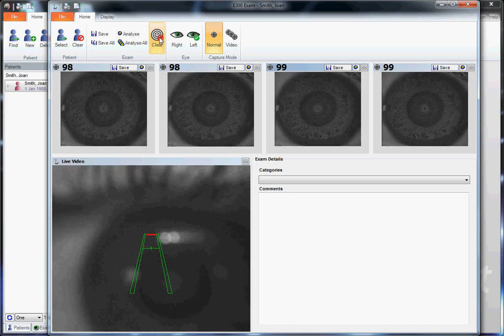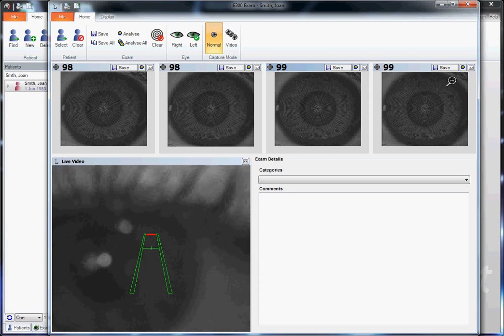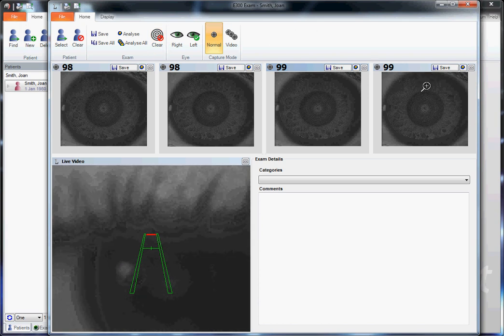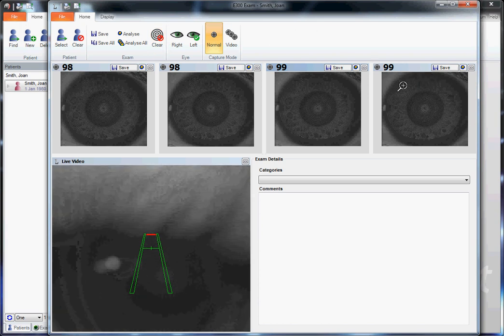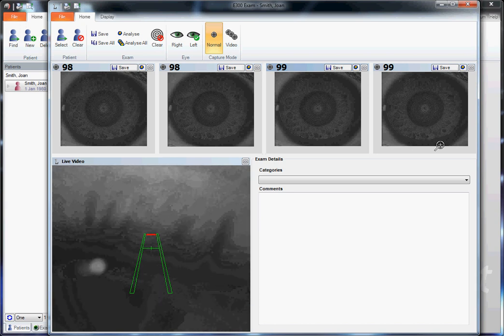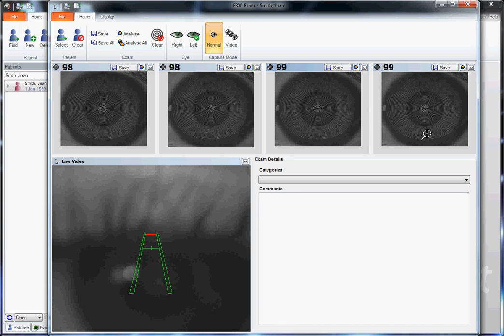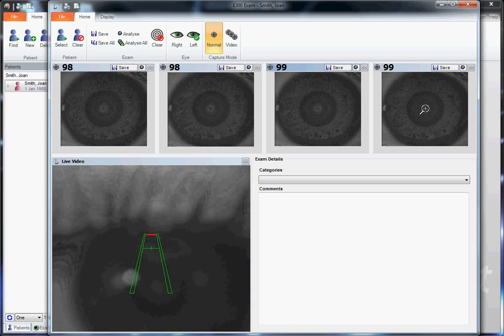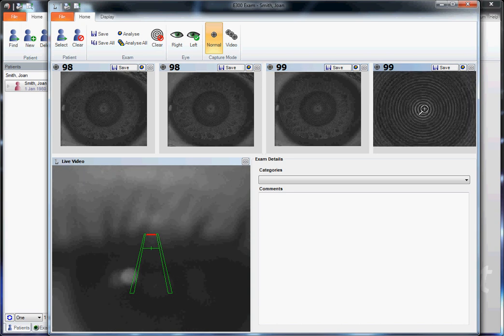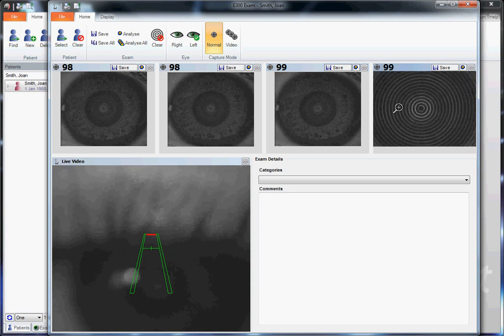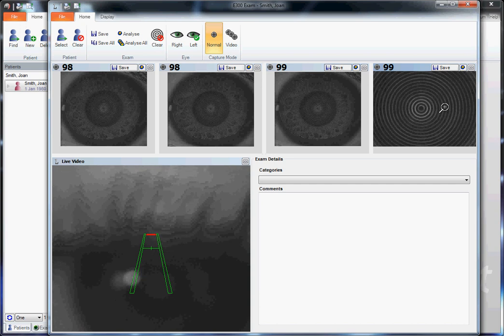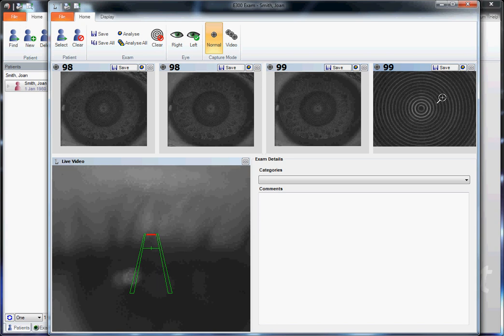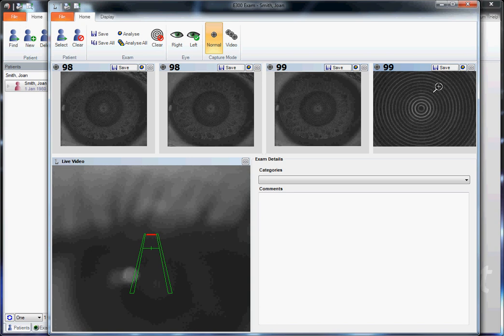And now we're able to see this beautiful Placido capture where the upper lid is out of the way, the eyelash shadows are minimized, and the lower lid moved off the inferior cornea, which allows for as much Placido reflection on the inferior cornea as possible. The key being to always zoom in and determine if the Placido rings look parallel and even to each other. If the reflection is ideal like you see in this image, then we can expect we'll have an accurate interpretation of eye shape.